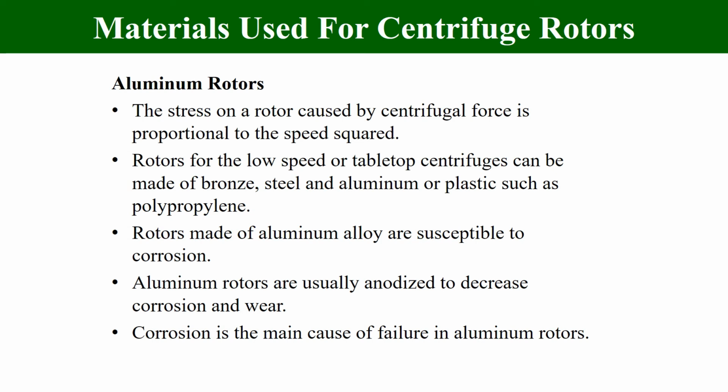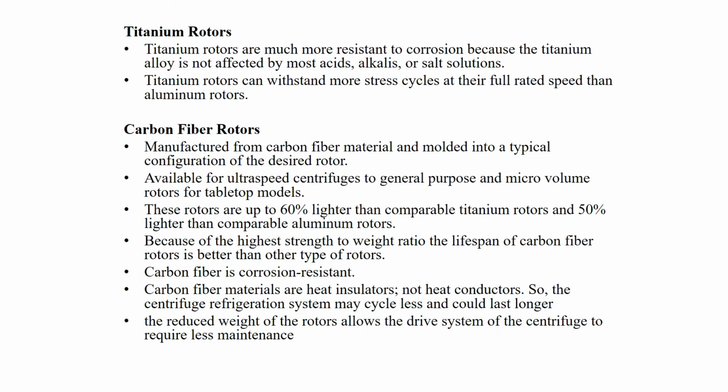So special care has to be taken in order to look after the rotor. Another kind of rotor is the titanium rotor. This has a lot of advantages over the aluminum rotors because titanium alloy can withstand high stress, it can withstand acid attack, alkali or salt spilling in the rotor. So these are some of the advantages of titanium rotors.